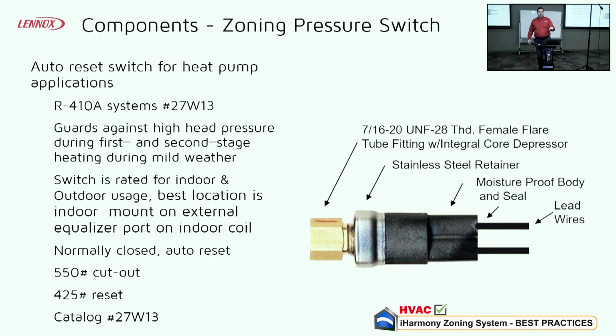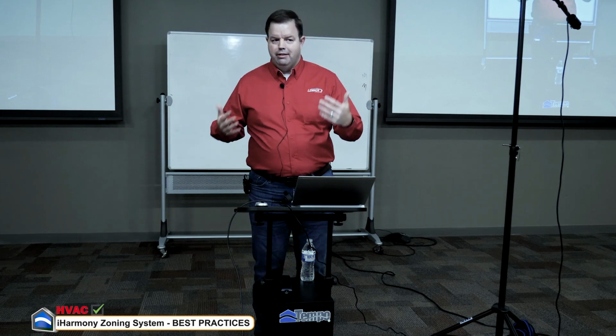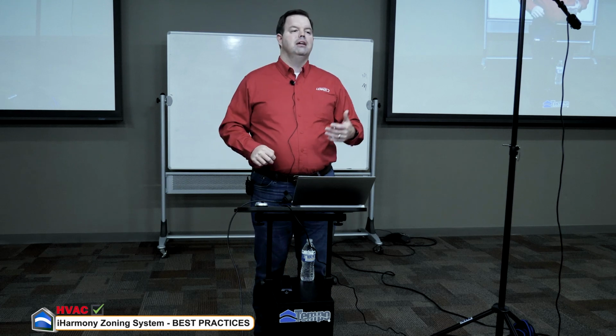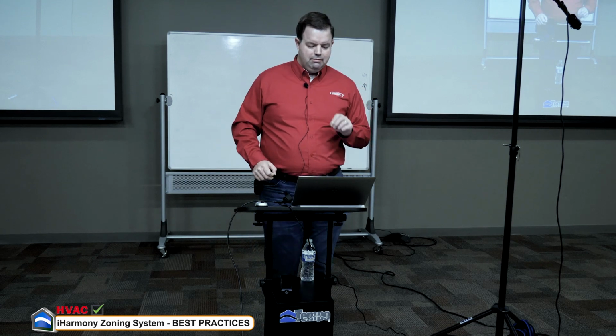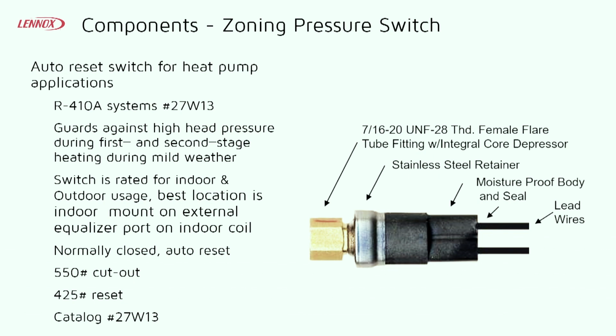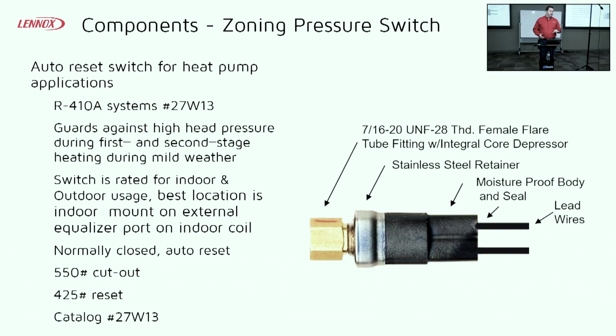If this isn't installed, then the zone system says, well, looks like the heat pump pressure is too high. No heat pump for you, I'm going straight to electric heat. And then the homeowner gets one of those nice $600-700 electric bills, and they're like, this piece of junk doesn't work. So this will save you a lot of headaches. I had a colleague at our corporate office who had a new system installed, and the dealer didn't put this in. She was having all kinds of issues with it, and that's what ended up being the problem, just a step they missed on installation. Any questions on this switch?